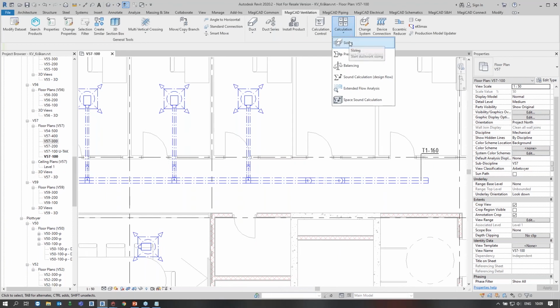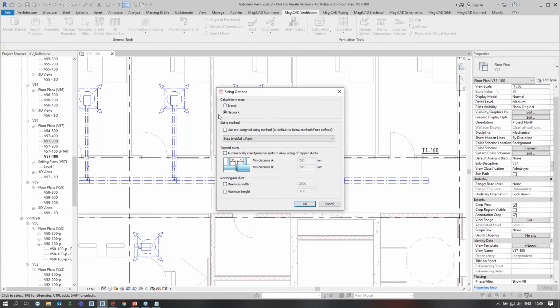I don't have any big warnings. But if I go for sizing and calculate the whole network, I'm going to use 1 Pascal per meter. If I had used rectangular ducts with a false ceiling, maybe I don't have so much space, so I could limit the maximum height to 400, but allow it to be much wider since I might have more space left and right than up and down.